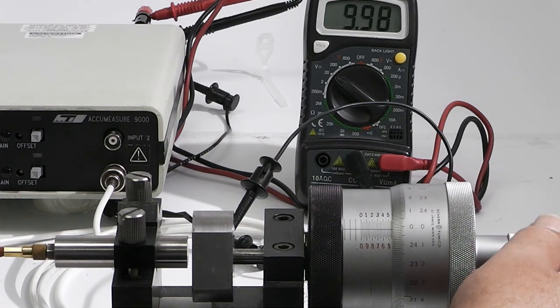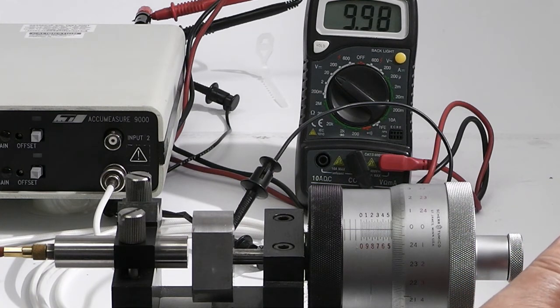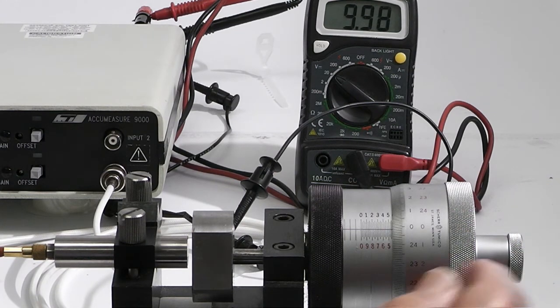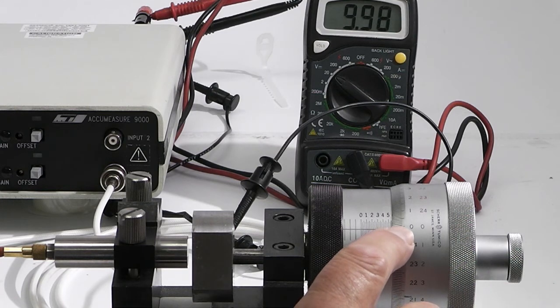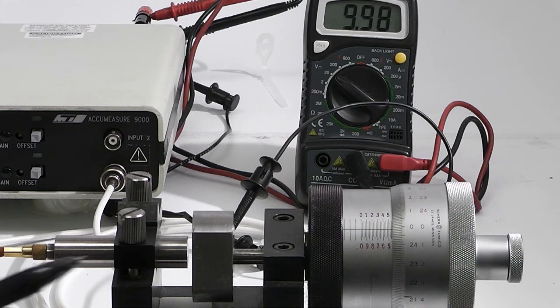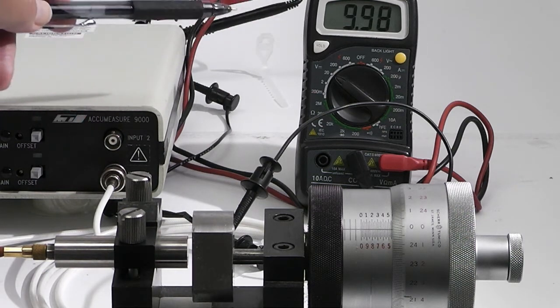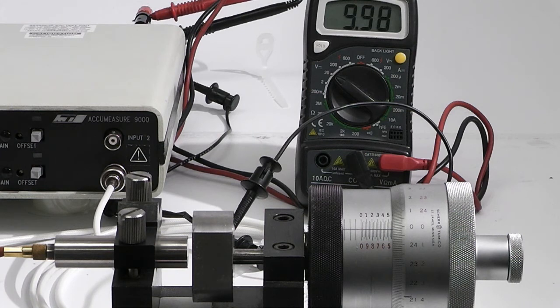As you can see in the previous step, we have rotated the micrometer 4 complete turns, and this corresponds, when it's resting at 0, to 2.5mm full gap. And we can also see the gap from the sensor probe to the target is 2.5mm. And if the display shows 10 volts, then the amplifier and probe are properly calibrated.